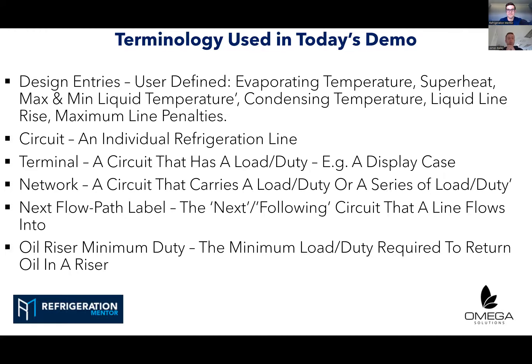Terminology you hear with MicroPipe: those who want a trial demo of the software, do reach out to me and Trevor. The software calls for design entries — user-defined inputs: evaporating temperature, superheat value, maximum and minimum liquid temperatures, condensing temperature, liquid line rises, and maximum line penalties. A circuit is one individual refrigeration line. A terminal is a piece of pipework that has a load or duty connected to it, like a display case. A network piece of pipe is a circuit that's actually carrying a load or duty. The next flow path label is very intuitive, simple, and logical to use.